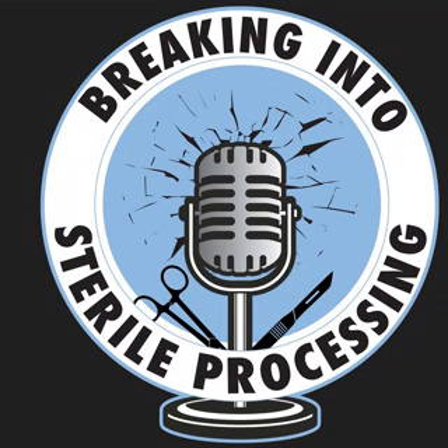Yeah. Decontamination is the messy, high-stakes beginning of the process. In the real world, if you fail to properly clean the bioburden off an instrument, the rest of the process is totally compromised. The bioburden being the blood, tissue, bone fragments, all that. Yeah, exactly. There's a foundational rule in this field. You cannot sterilize dirt. If the organic soil isn't meticulously removed in the decon area using the right enzymes and water temperatures, the sterilization cycle will just fail. Because the sterilant chemicals can't penetrate that barrier of soil. Exactly. That's why it's a massive 21% of the test.